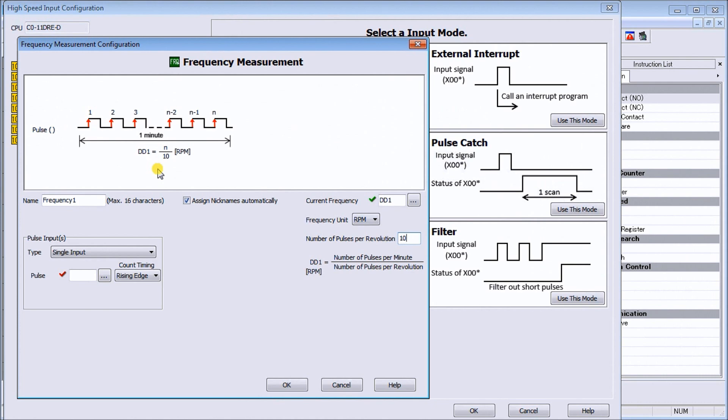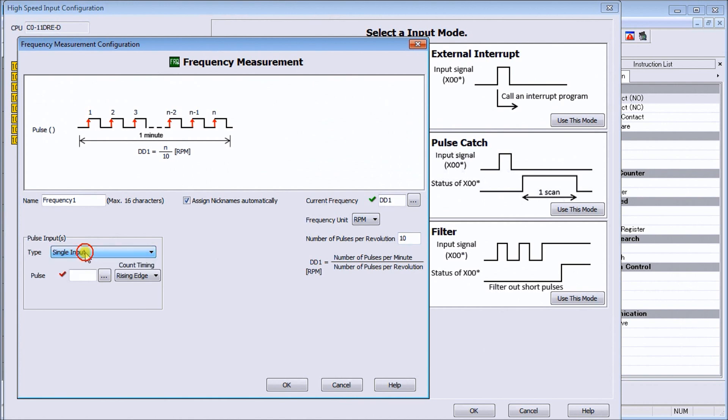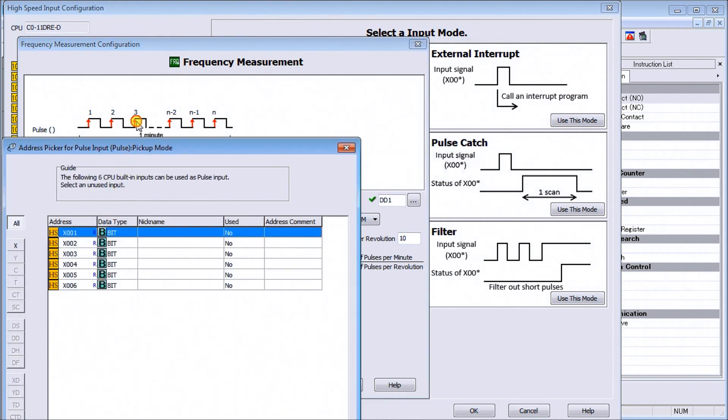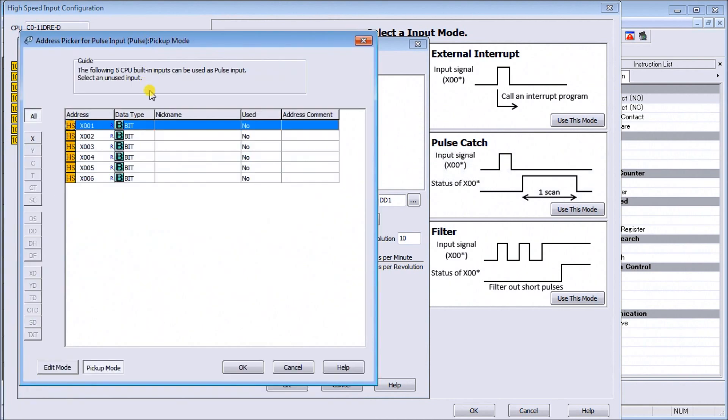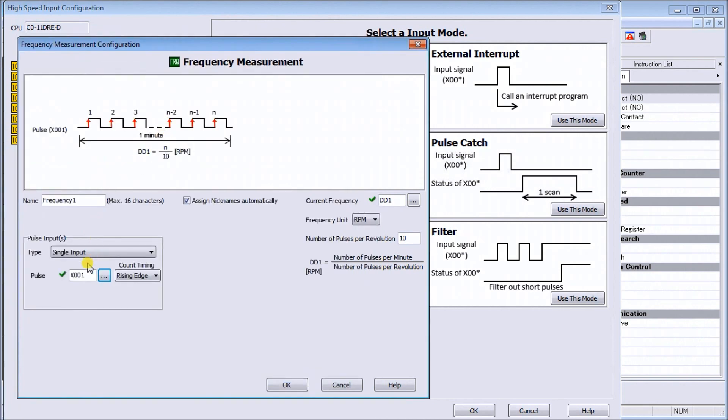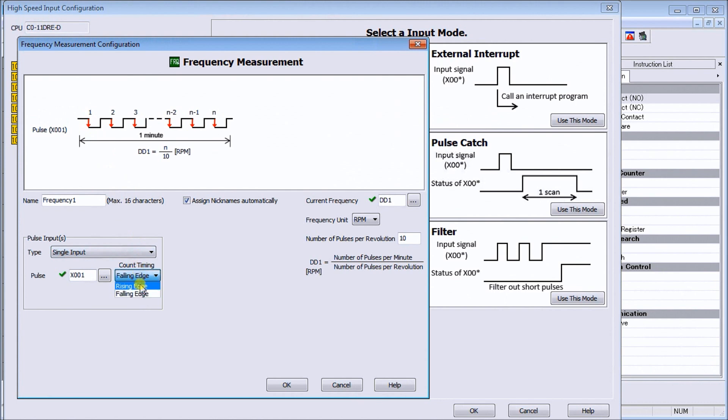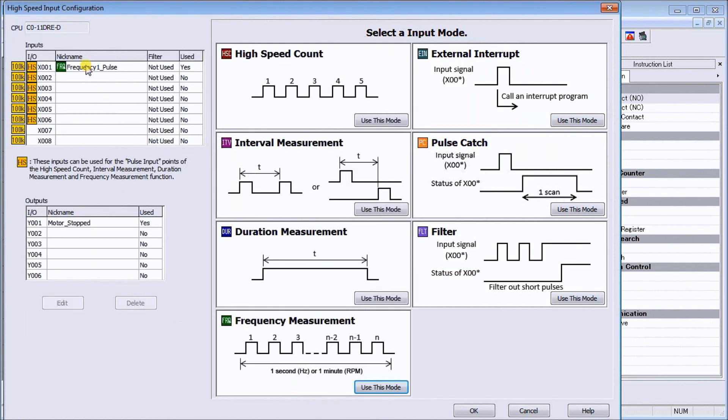So we'll leave it like that. And then we have here our pulse input - we have a single input. We could do a quadrature as well which gives you an A B phase, but we have a single on the start and we can select our actual input which is X1. We'll look at the rising edge - we could actually look at the falling edge which is the opposite side, but we'll leave as default on the rising edge. So that is our setup here, we'll hit OK.